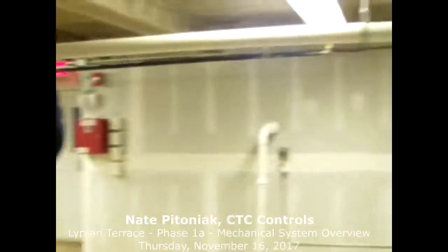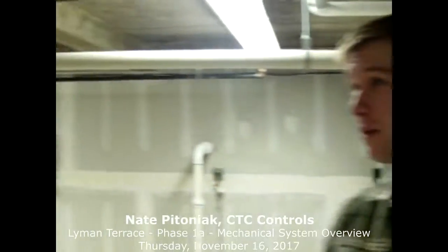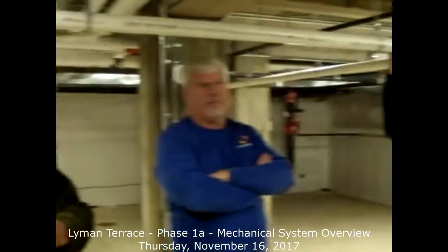Yep, so you'll know if the thermostat is blank, look for a power problem. And good peace of mind, all of the zone valves we have in your building, they all fail open. So if you lose power in the middle of winter, you're only going to make them more toasty. Are they automatic? That's a good feature. Most zone valves do not do that. And the zone valves are in the units.